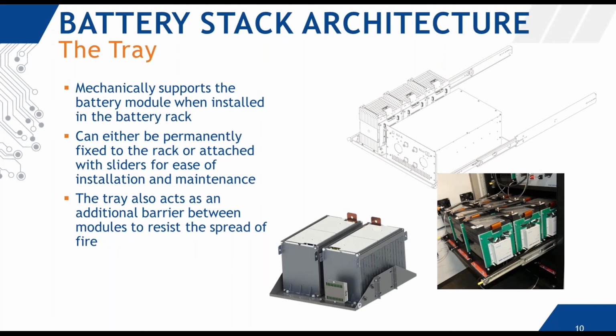And those modules are then put onto a tray, because we need some sort of way to hold them. And that tray can either be permanently mounted or it can be affixed with sliders. And that sort of decision comes down to installation and maintenance. And the installation and maintenance plan is actually reviewed as part of 1973. So that's like requirement 42. And so to design this properly, we're looking at a tray that is considering weight, the working area around it, and the type of maintenance operations that could be carried out. So if we were, every year or so, retorquing high current connections, well, a slider would be more appealing than a permanently mounted tray.